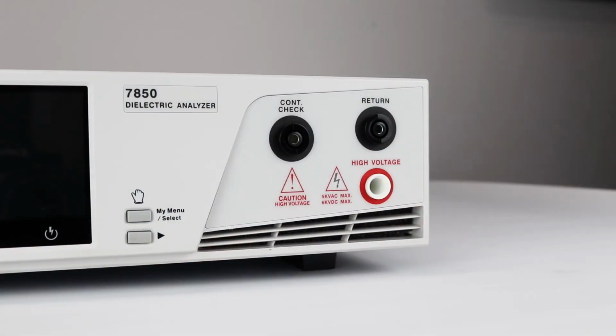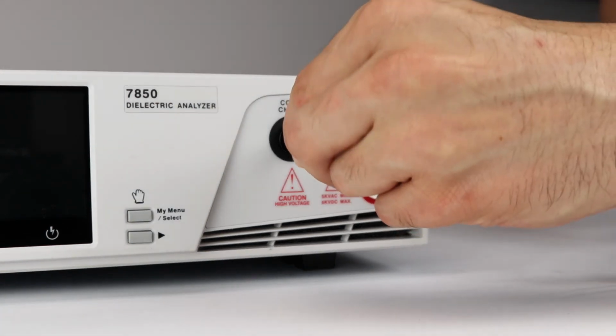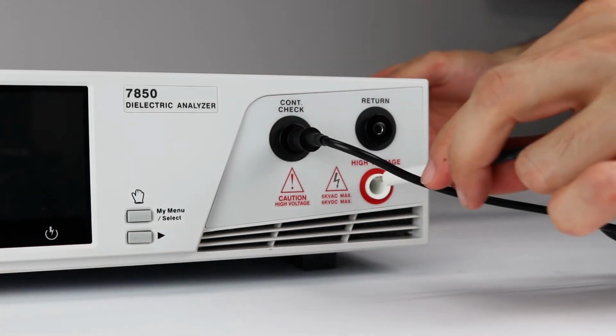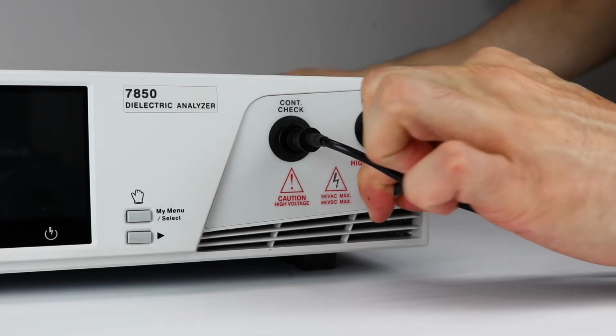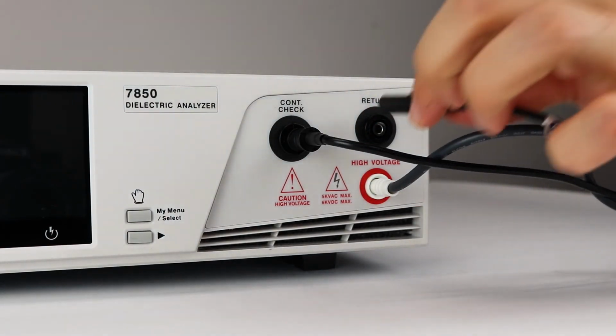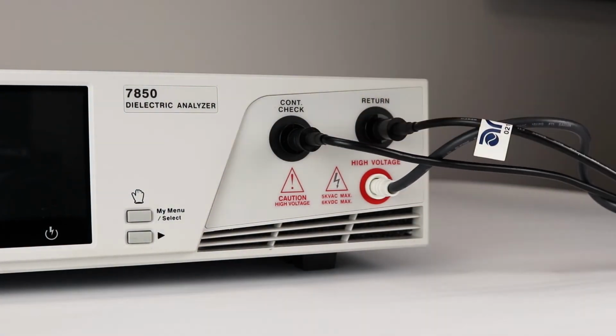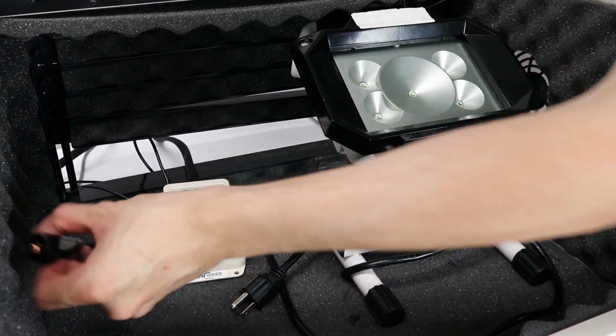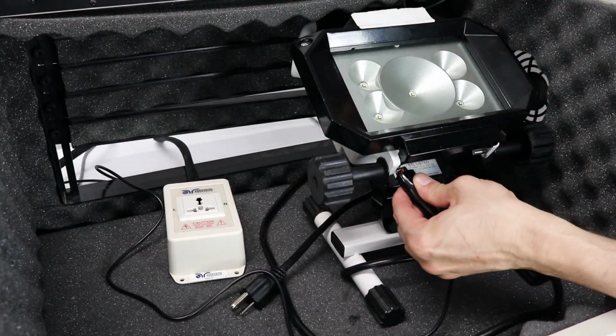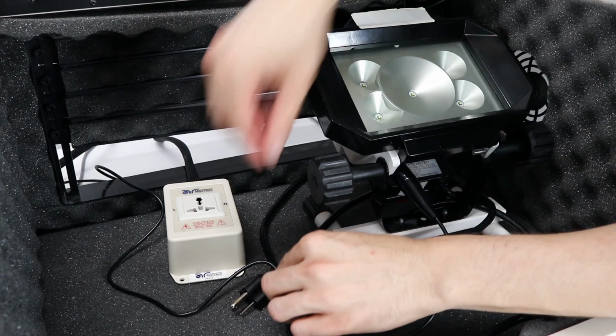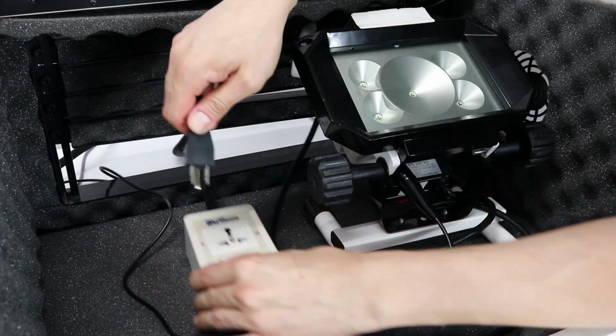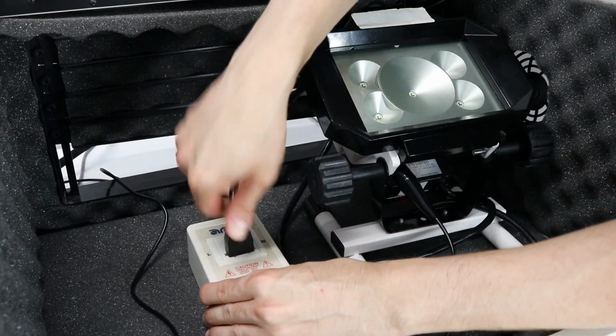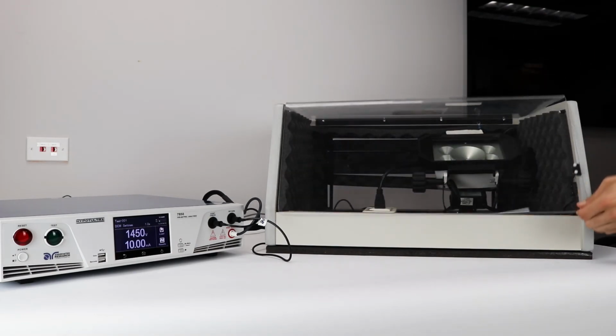If you're using the universal style adapter box instead of the scanner channels, connect the adapter box to the continuity check and the HV terminals. Then, connect the black lead to the return terminal. Simply connect the return lead to the chassis of the DUT. Then plug the 3-prong cord to the DUT into the adapter box. Close the DUT enclosure door.